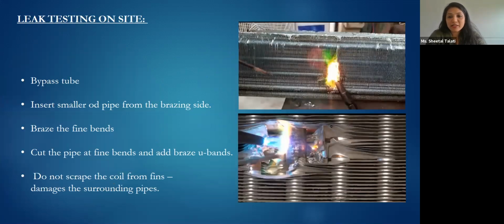Coming on to a very interesting part of this presentation: how do you leak test a coil on site? Looking at this picture, this is the major mistake that everybody makes while repairing a coil on site. They just tear off the fins and start brazing where the leak is. This is not what we recommend, and this is a completely wrong way to do it. What should you do when a tube is leaking in a coil?